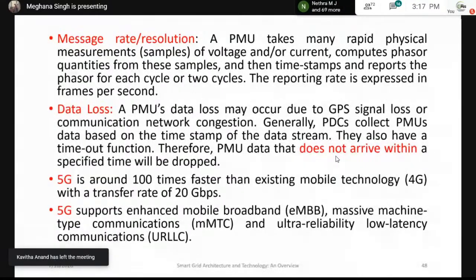PMU's data loss may occur due to GPS signal issues or communication network congestion. When data is to be sent in a particular time frame, it has to be sent. So generally, PDCs collect PMU data based on the timestamp of the data stream, and they also have a timeout function. Therefore, PMU data that does not arrive within a specified time will be dropped, meaning whatever raw data comes late is treated as junk data and not accepted.